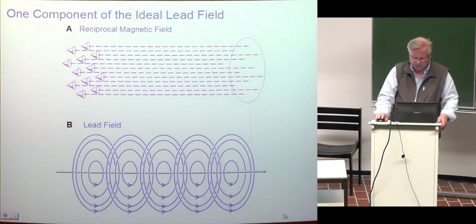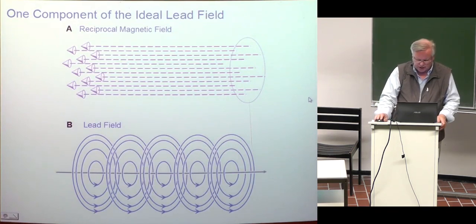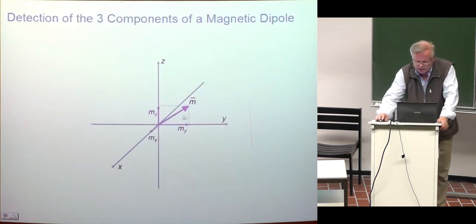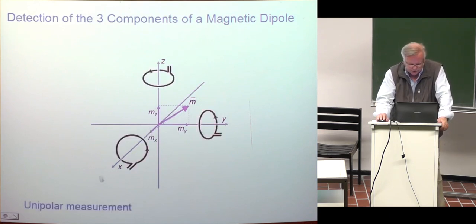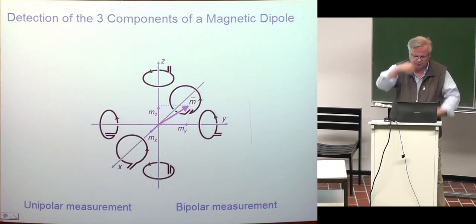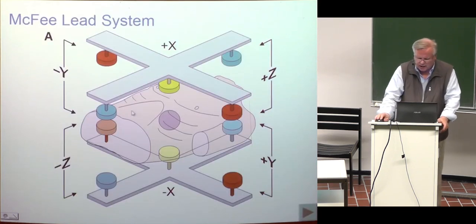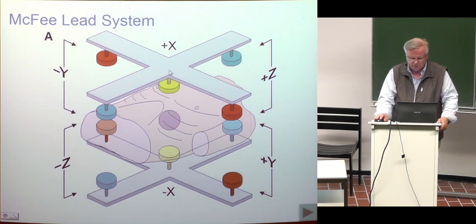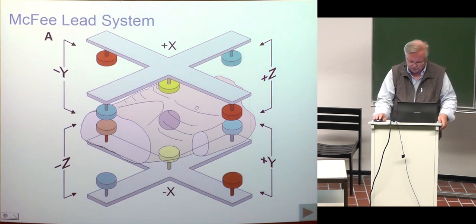To detect the magnetocardiogram, measuring the magnetic dipole requires three orthogonal lead fields. The magnetic dipole has three components: X, Y, and Z. They may be measured unipolarly with three coils, but better signal quality is obtained with bipolar measurements having two coils on both sides of the source. The first magnetocardiographic lead system was suggested by McFee — theoretically okay, but practically it would not work because it collects a lot of noise.